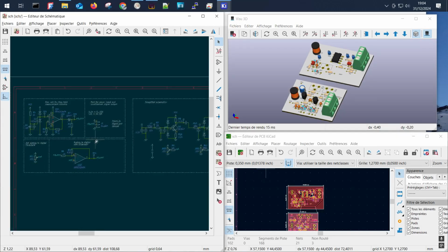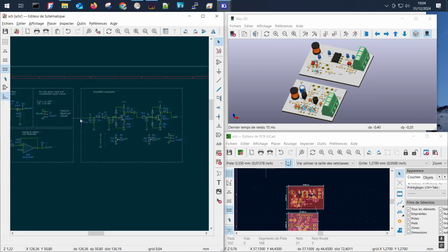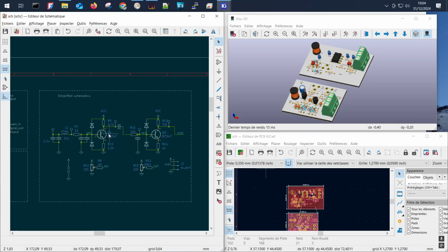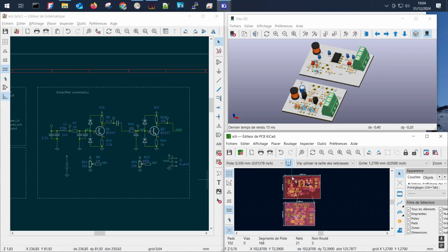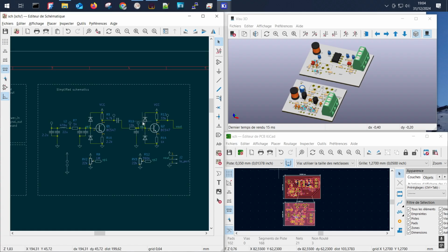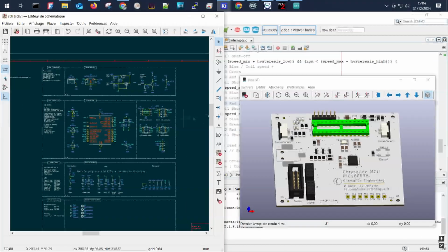We also needed to develop the boards that issue the pulses. The speed detection is just a coil and a magnet, and then we have an amplifier and a pulse generation. The signal input is a 100 millivolt sinus pulse, and the output is from 1.5 to 5 volts, with a 1 millisecond to 10 or 15 millisecond square edge pulse, roughly speaking. We see the design over here.